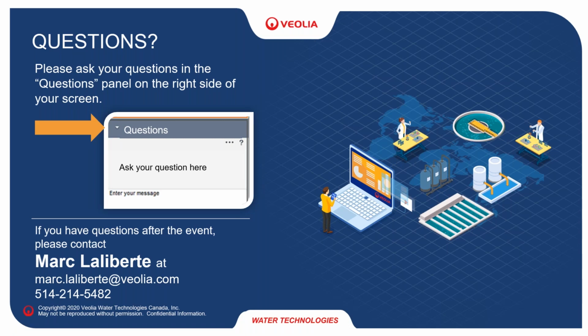As I said earlier, the systems I presented today are optimal between 500 and 10,000 cubic meters per day. For American people, that would be roughly 200 to 2,000 GPM, something like that. We can do more, we can do less. Less, usually it's better to go batch treatment, which is possible, but I didn't present it today.